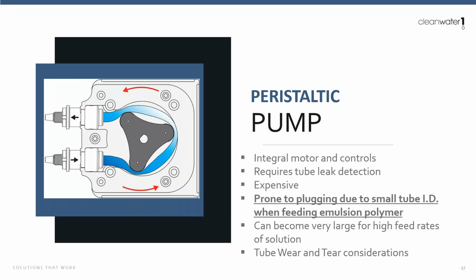Another option that we will see is peristaltic pumps. These are kind of cool because you can have an integral motor and controls, but they do require tube leak detection. We want to know immediately if something happens to that tube, if it breaks, if it's leaking, because it can cause a gigantic mess if we aren't able to shut down that pump. One of the downsides of using a peristaltic pump is for a high-end peristaltic pump, they're generally much more expensive than a progressive cavity pump. And in regards to neat polymer, they can be prone to plugging due to the small inner tube diameters.